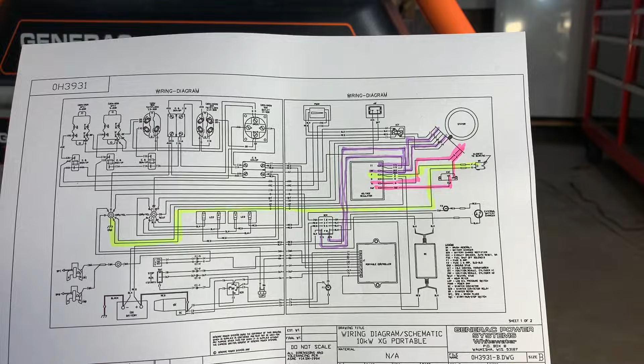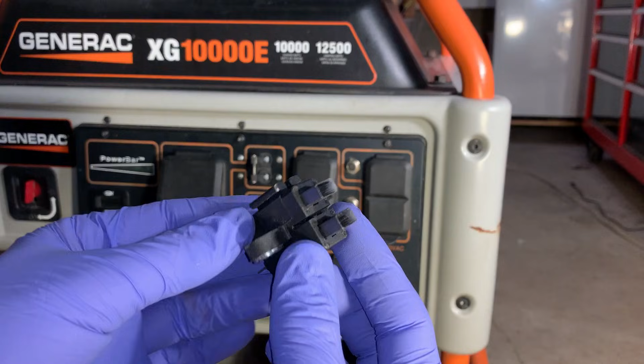I went to reconnect the brushes to do that test, and ended up pulling the brushes off for two reasons. One, I wanted to see how much meat was left on these, and they're in very good shape given the hours on this generator, so they've probably been replaced at one point.